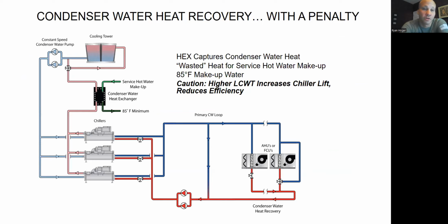So by energy code, you have to start recovering energy from that condenser water in those kind of winter times, right? So this is the same kind of idea, just a little better drawing. We got air handlers with fan coils over here, right? We got our pumping system. This is all of our chilled water loop over here. This is a primary only loop, not a primary secondary. I got 3 chillers in this case, right?